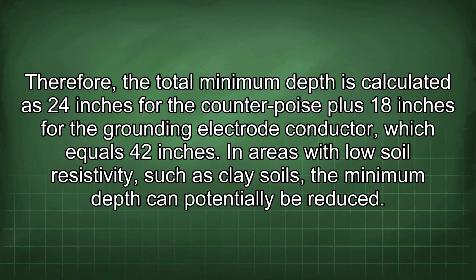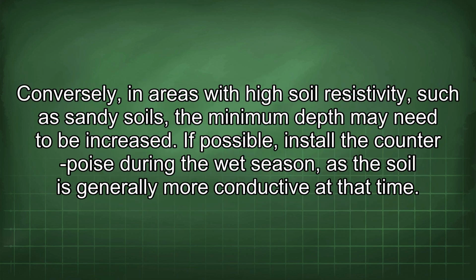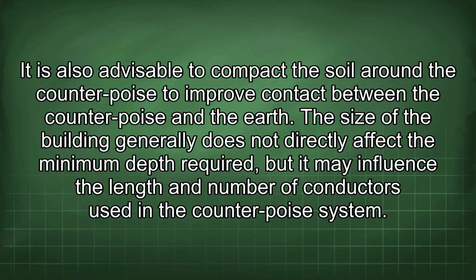In areas with low soil resistivity, such as clay soils, the minimum depth can potentially be reduced. Conversely, in areas with high soil resistivity, such as sandy soils, the minimum depth may need to be increased. If possible, install the counterpoise during the wet season, as the soil is generally more conductive at that time. It is also advisable to compact the soil around the counterpoise to improve contact between the counterpoise and the earth.